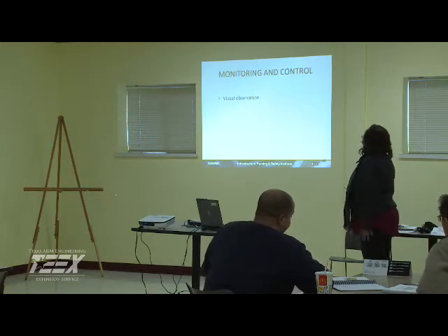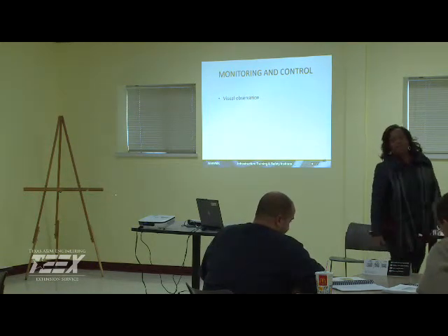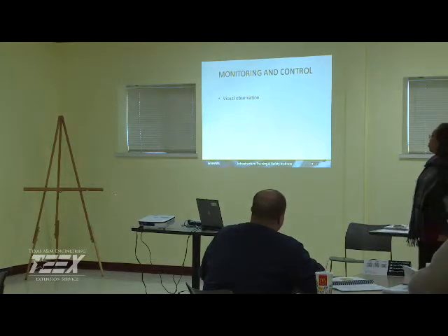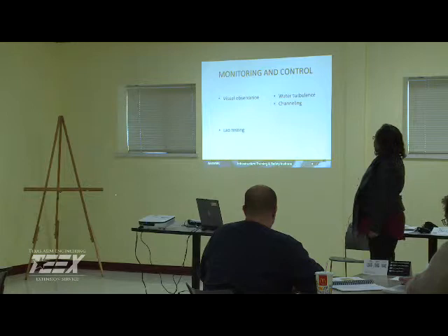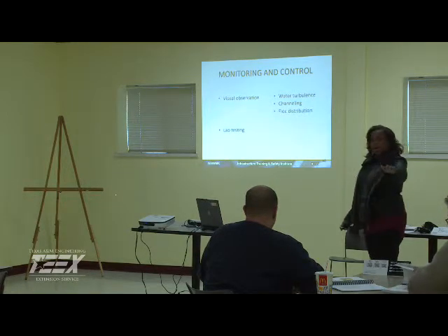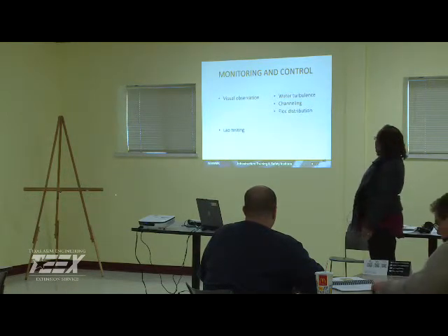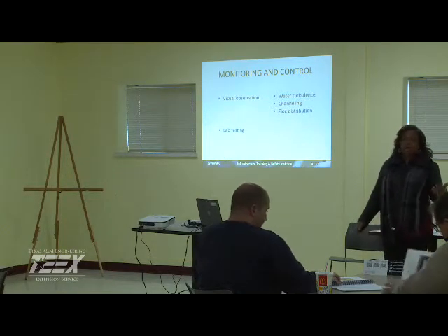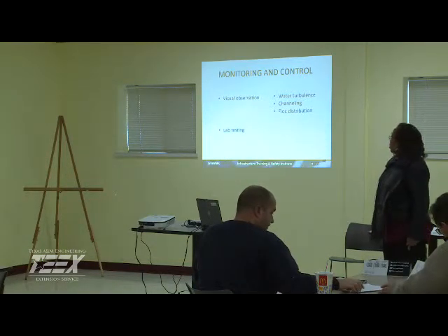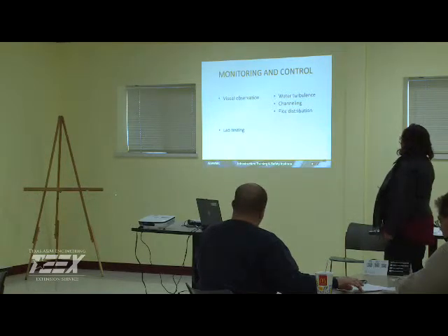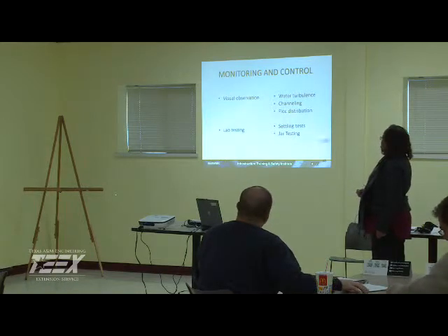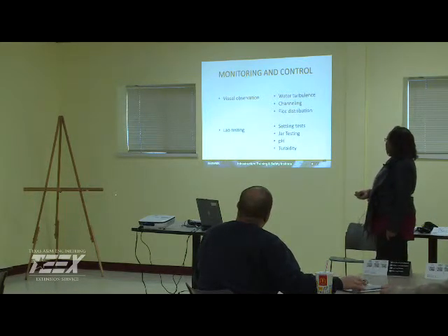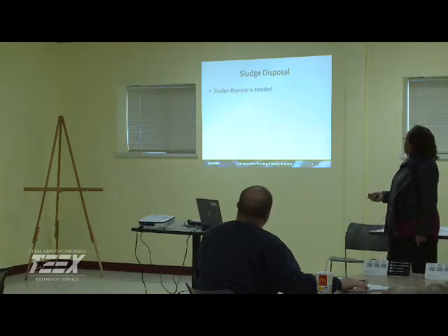Monitoring and control of the sedimentation tank: you're doing visual observation. We're looking to see whether or not the floc is settling, water turbulence, and channeling, if that's occurring. That's another way of saying short circuiting, and floc distribution. You want to do settling tests, jar testing, and pH, as well as looking at the turbidity.